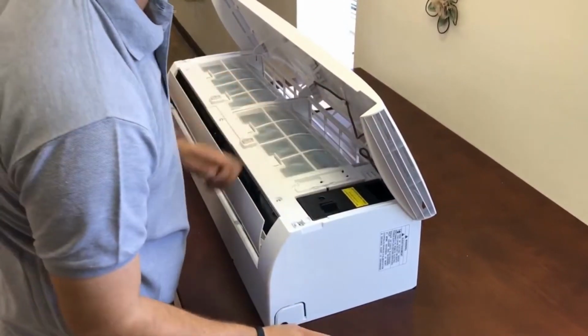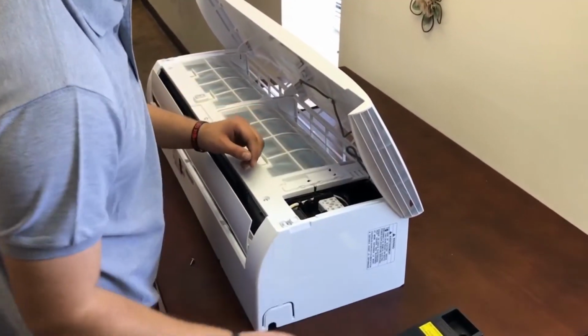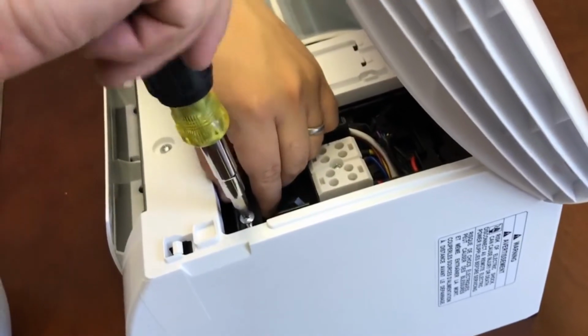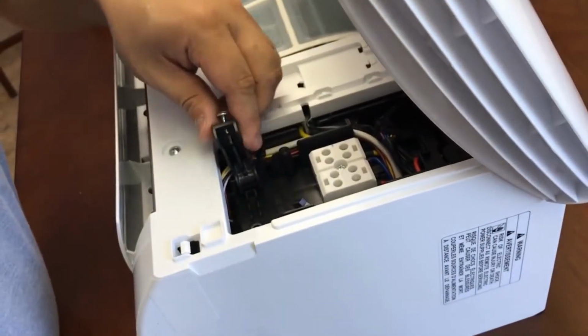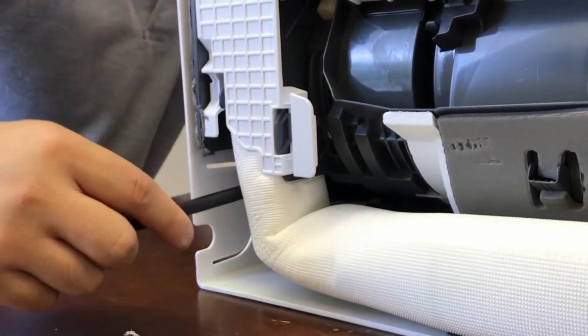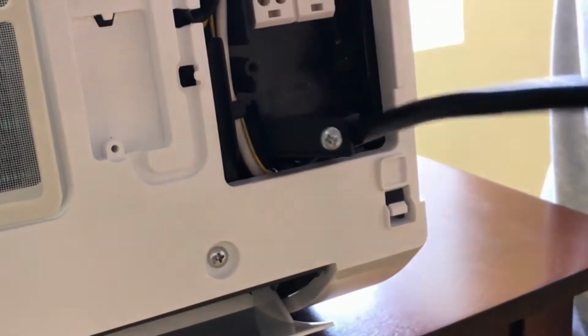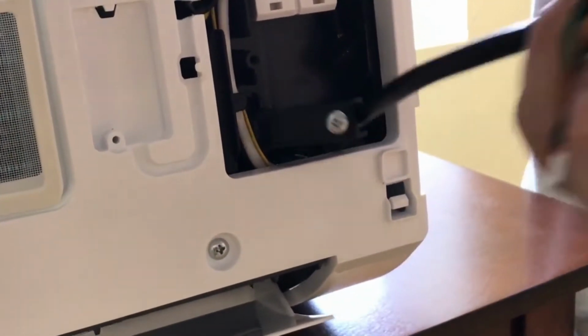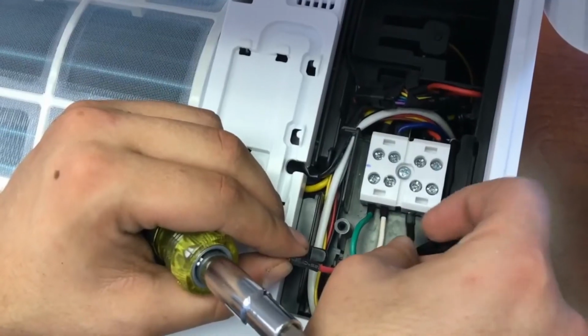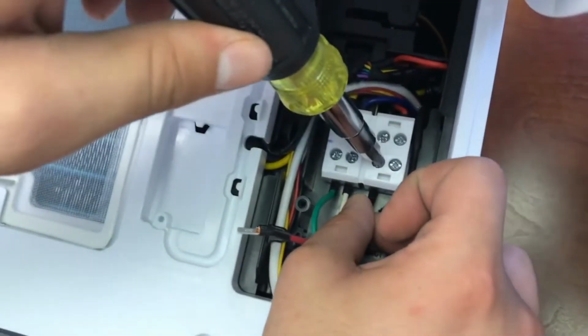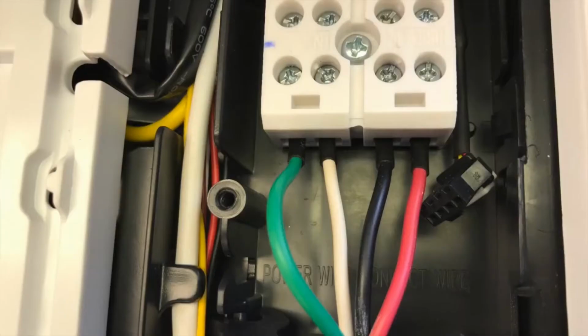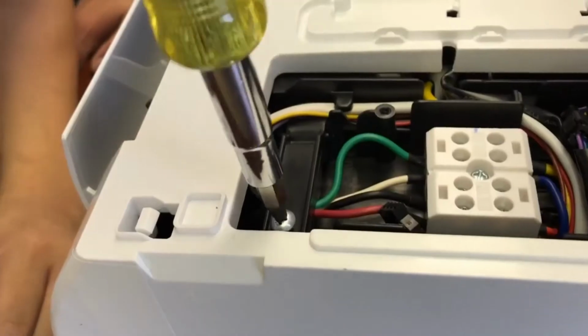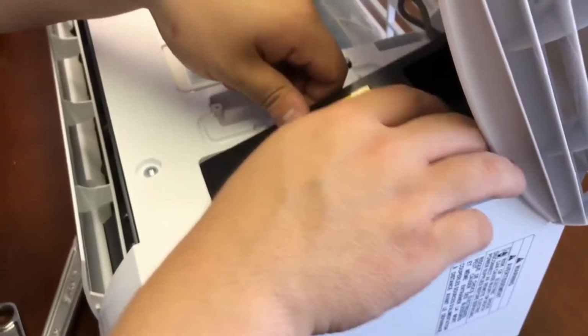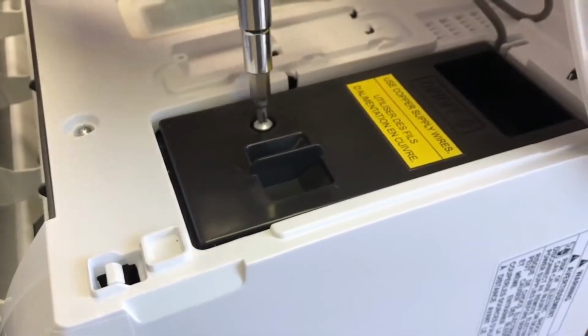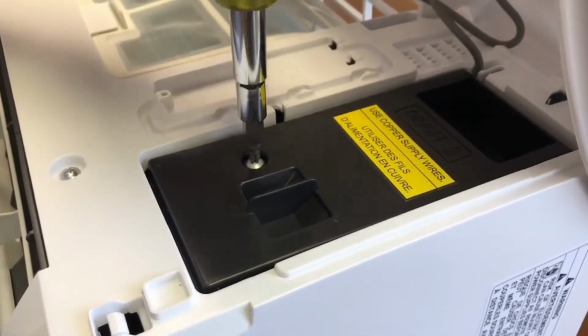Prepare to install the control wire by removing the wire cover and wiring clip. Push the color-coded multi-conductor wire through the inlet hole on the back of the air handler and pull a few inches through the front. Now you can make the multi-conductor wire connections. After cutting the length and stripping the wire, make the connections using a screwdriver. Replace the wiring clip, wiring cover, and close the front cover.